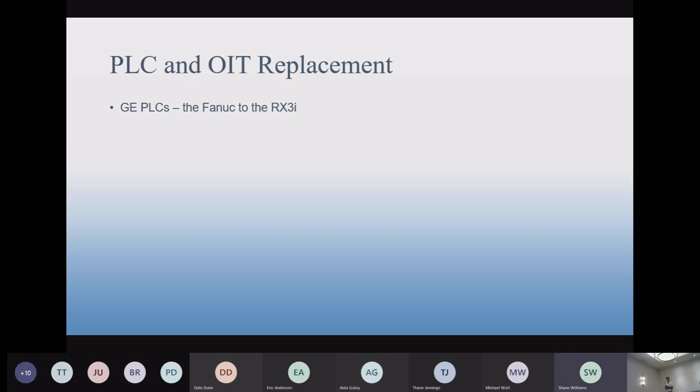PLC, is there an updated line control that we recommend? Yeah, we can use a lot of controllers typically. We do some easy control with the PLC as well. We like the Wago because we think it's more robust, in my personal opinion. The contacts on PLCs definitely fail after some time. You can have some problems with the solid state contacts on PLCs.